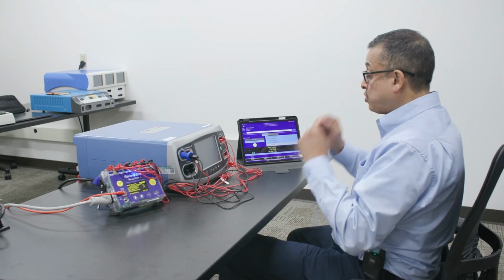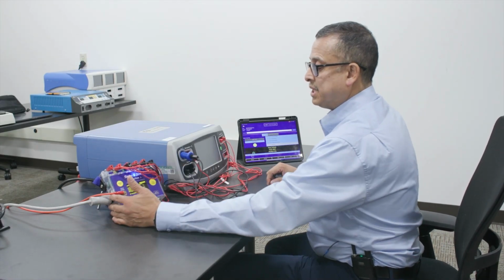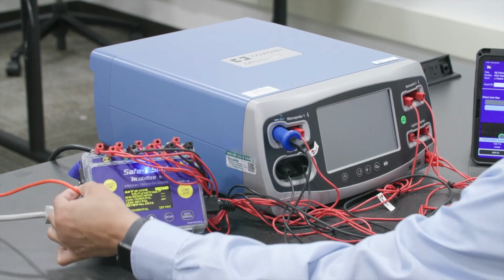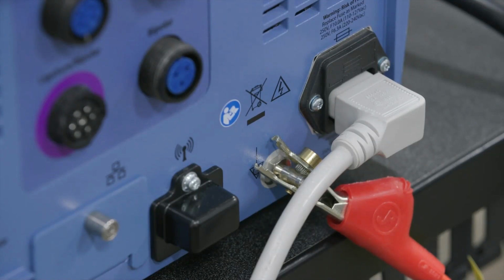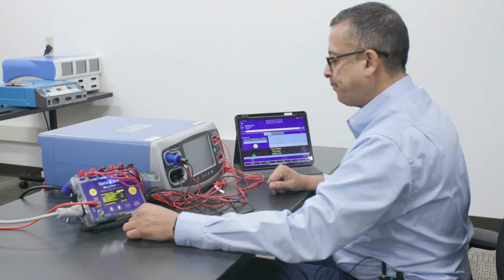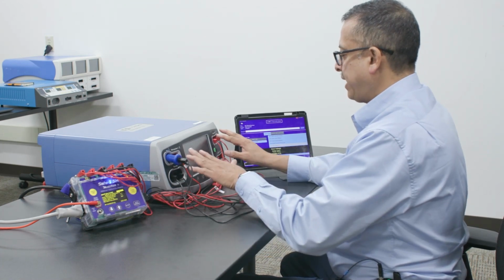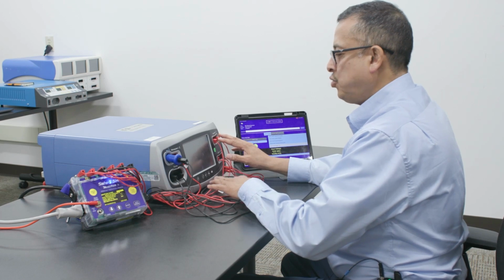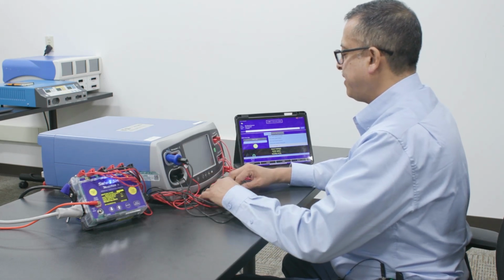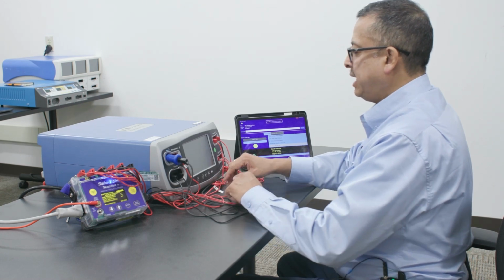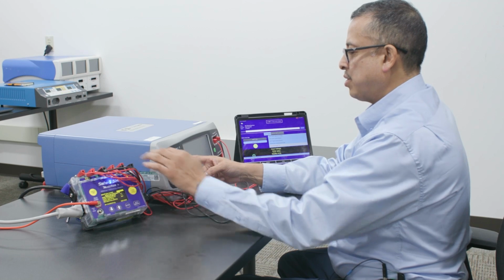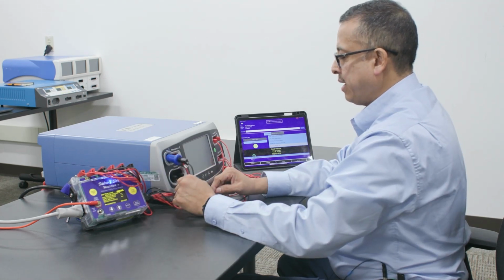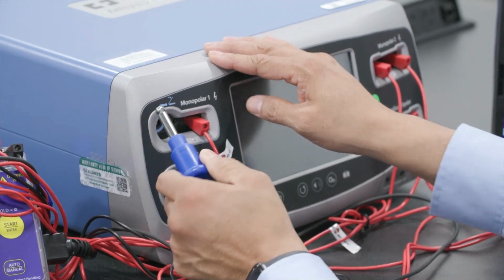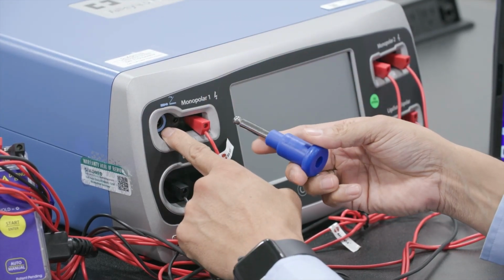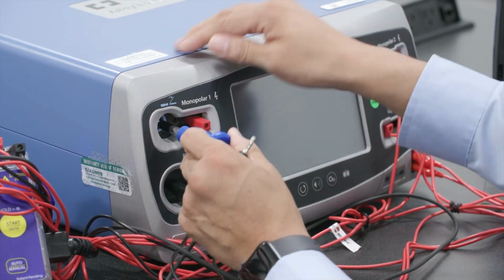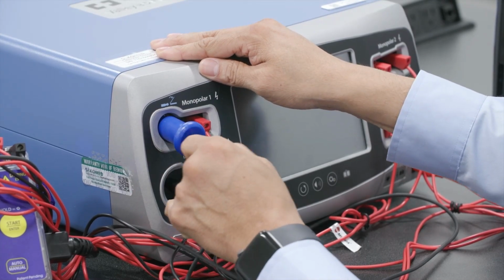ESU. Before we do that, of course, we need to connect our ESU up to this electrical safety analyzer here on the left side. We want to connect our red test lead cable to the ground post on the back of the unit for our ground resistance testing. And then we need to connect what they refer to as all the outputs or applied parts to the electrical safety analyzer. We're going to do this using a set of banana to banana lead wires, connecting each port to the safety analyzer applied parts section, which is up here in the ECG snaps area. To do the first port on the FT10, you have to use a special adapter for the very far left port on the monopolar one. So we'll need to have this plugged into this side, and then we can connect our banana plug to that.